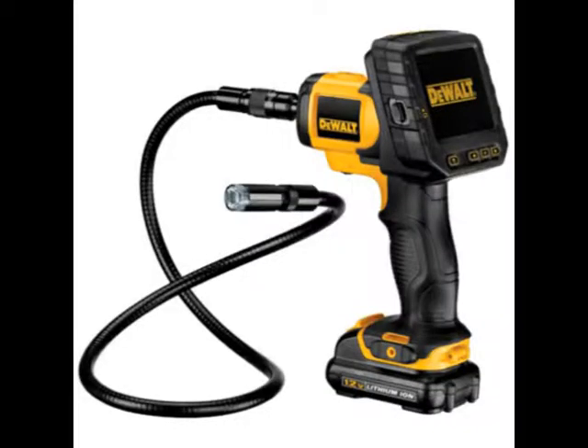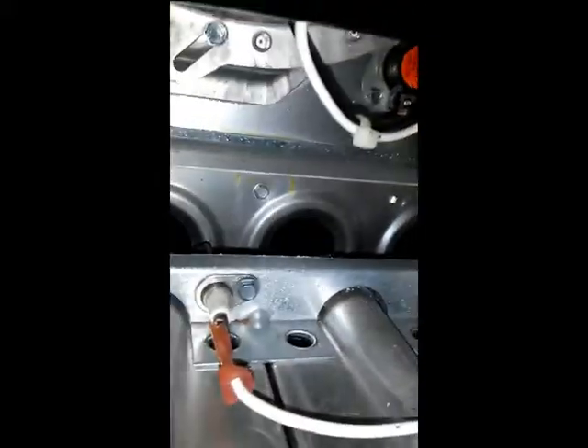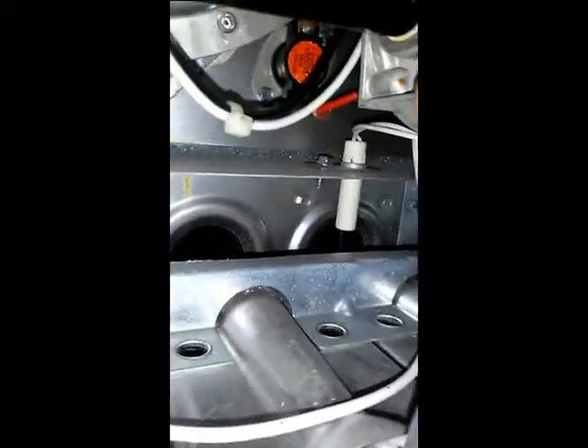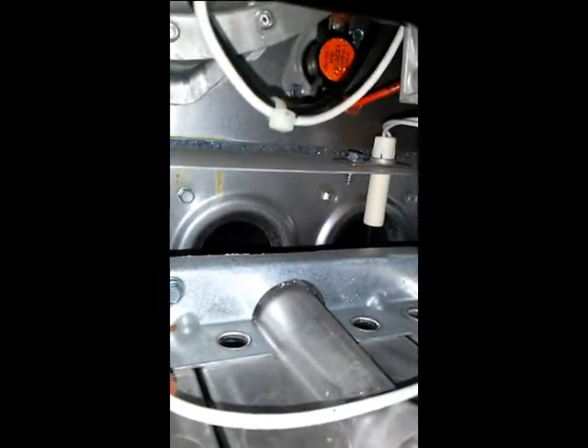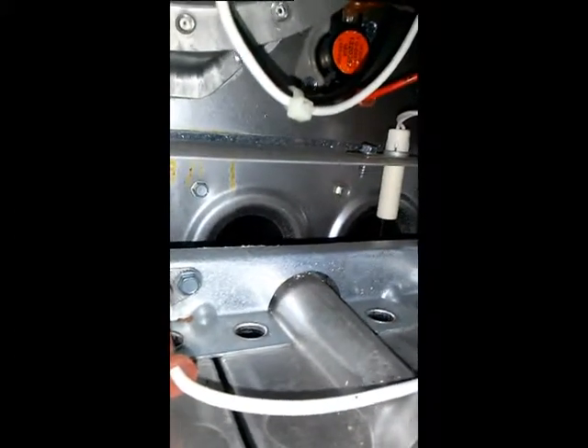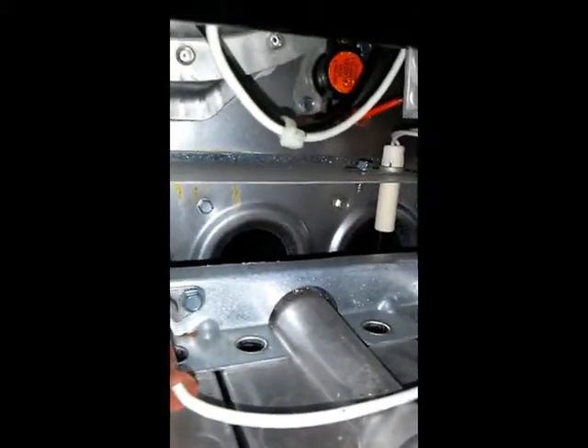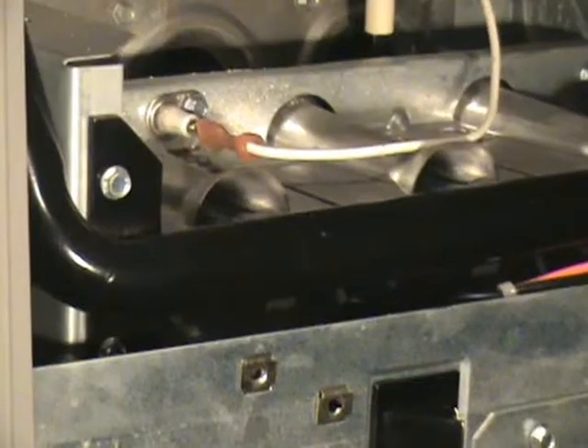We also have inspection cameras too. If I couldn't get in through the plenum and needed to inspect the heat exchanger, I would pull that high limit out and stick my camera in there just to see if I could see anything that way. But another way to do it is to actually pull this whole motor out and crawl in there to look up.